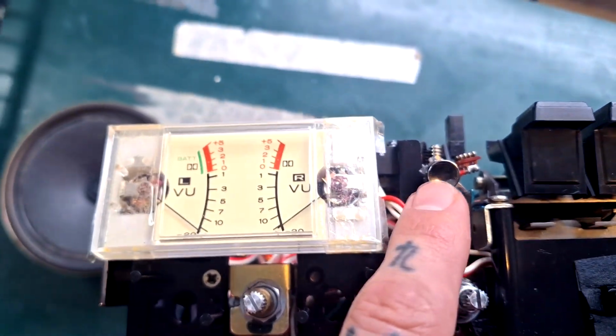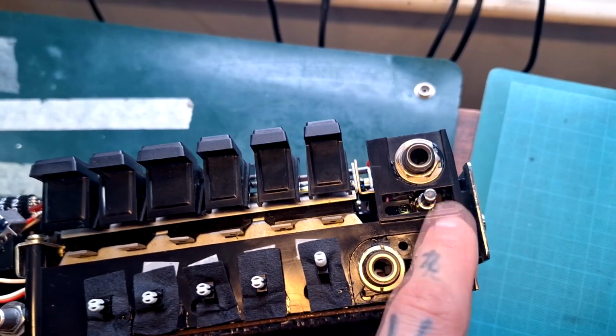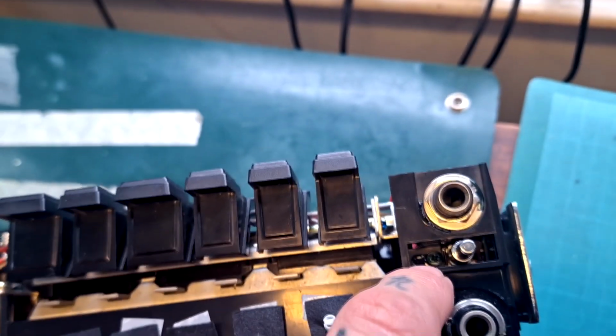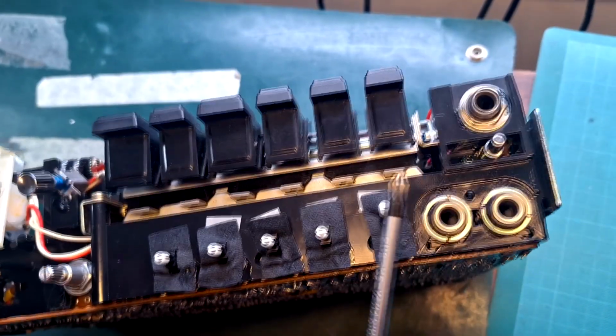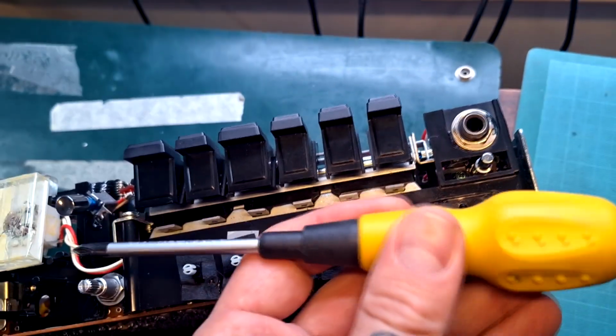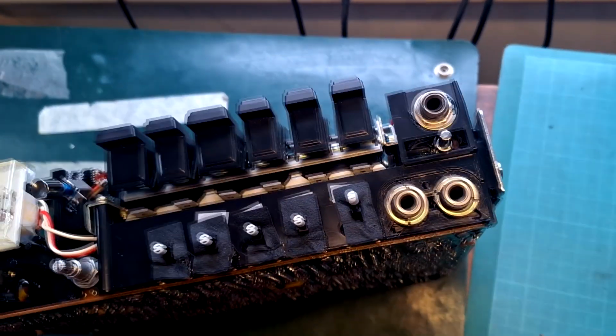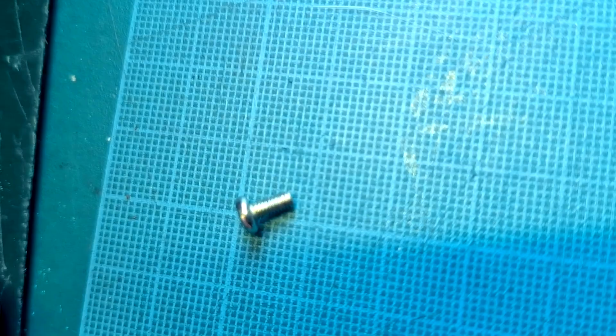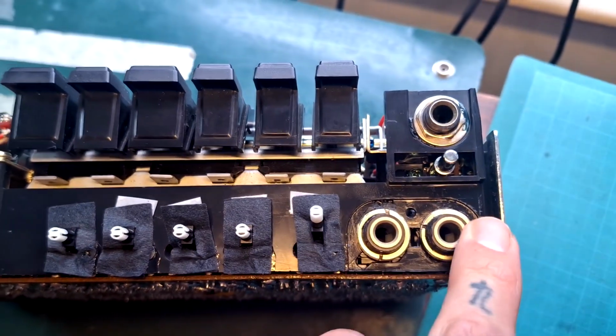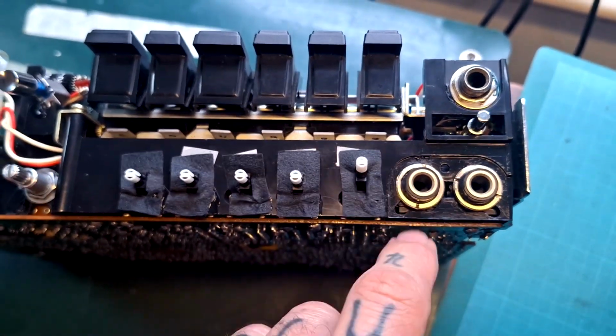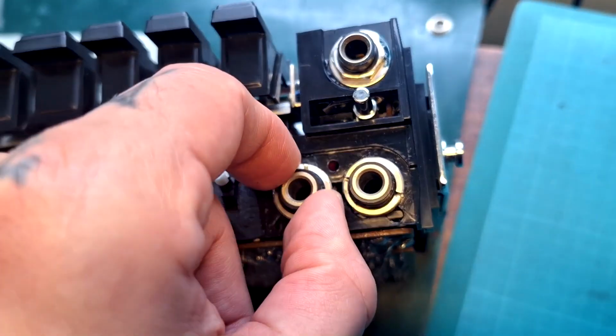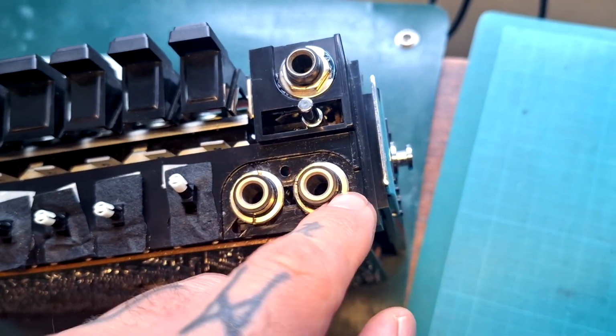The battery check switch and the mic attenuation switch are both held in place with a single screw. We need a smaller crosshead or JIS screwdriver for that. This is what the screw looks like, maybe 7mm in length. And then these 2 microphone input sockets are held in place with, I don't know if we would call it a nut, but certainly it's threaded and threads onto this black plastic thread.